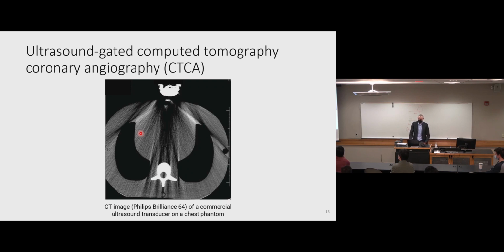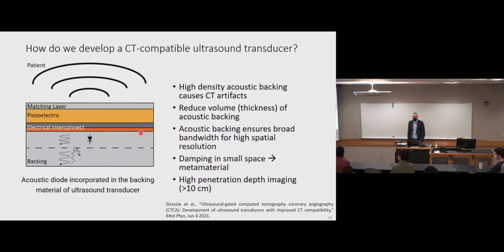So the problem here is, how do we develop an ultrasound transducer that's CT compatible, or that we could use at the same time the CT images are being acquired, without producing those terrible artifacts that result in the non-diagnostic scan. So I realize some of us here are probably ultrasound experts and know all this, but on the left side of this slide, I'm showing the quick cross-section of a piezoelectric ultrasound transducer. So this is kind of the anatomy of the ultrasound transducer. It's definitely not drawn to scale.